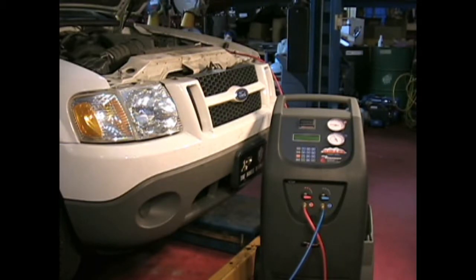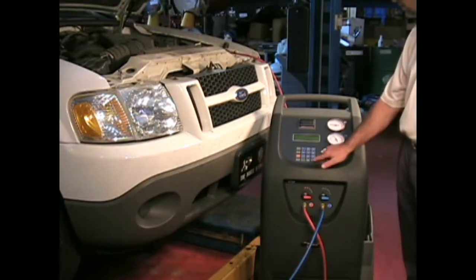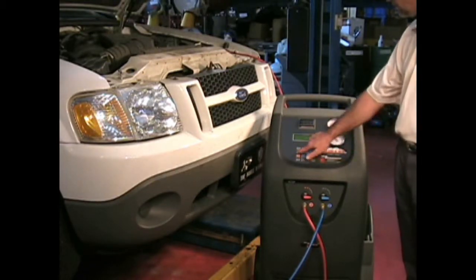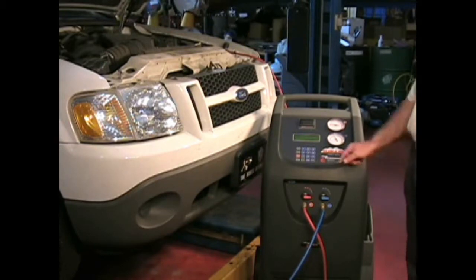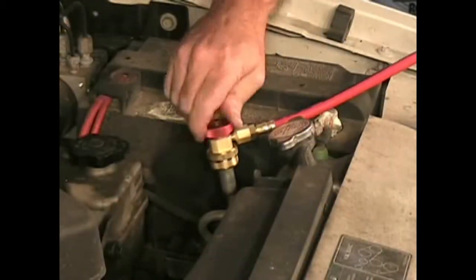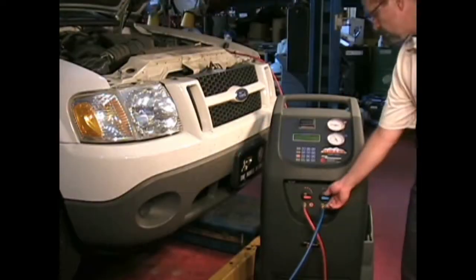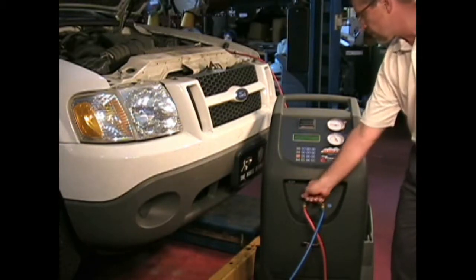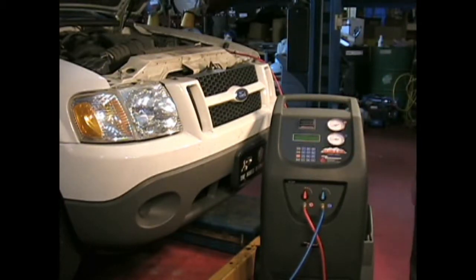Assisted operation lets you perform one function at a time. Should you only want to recover and recycle, arrow to Assisted Procedure and press Enter. Then press Enter again. You will be prompted to open the couplings and the machine taps and then to press Start. The machine will recover until the system is in a vacuum.